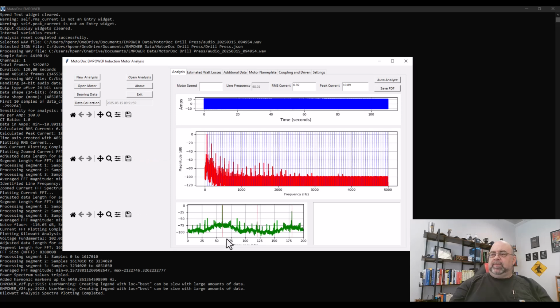So there would be a peak at about 120 hertz, right there. There's a double peak, indicating it's probably 3600. There's also a peak just under 90 hertz, which could also be running speed. But then I've got these peaks out here based upon what's probably 28 rotor bars.